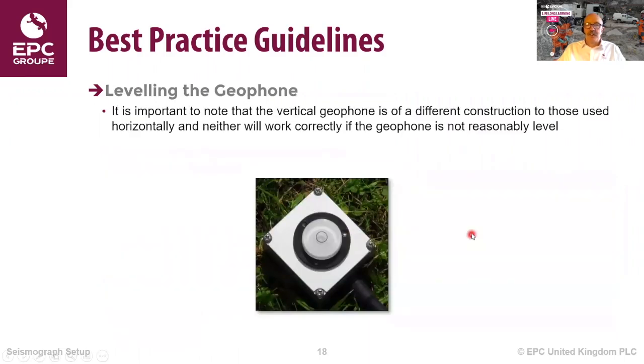Those geophones that we saw earlier on, the vertical and the horizontal ones, are of different construction. So it's important that the geophone is reasonably level. So you can put a little bubble level on top and just check that the geophone is level.